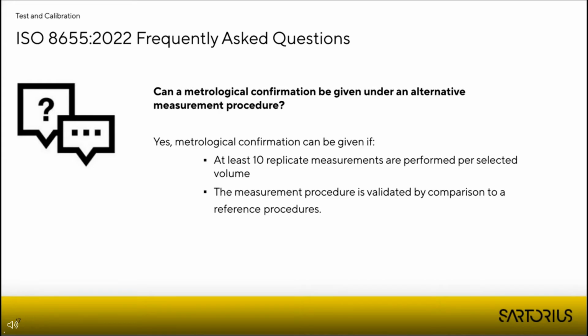Let's go on now with an important question that may come up with reference and alternative measurement procedures. Can a metrological confirmation be given under an alternative procedure? The clear answer here is yes, a metrological confirmation can be given, but there are 2 requirements that need to be fulfilled. First, at least 10 measurements must be performed per selected volume. And second, the measurement procedure must be validated by comparison to a reference procedure. If both requirements are fulfilled, a metrological confirmation can then also be given under part 7 of the new ISO.